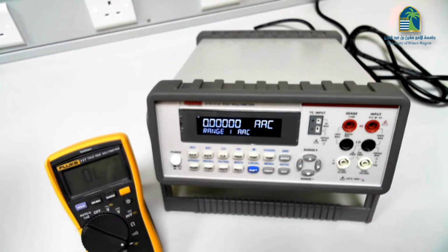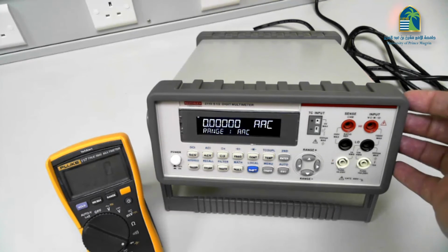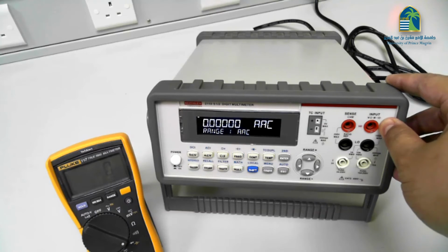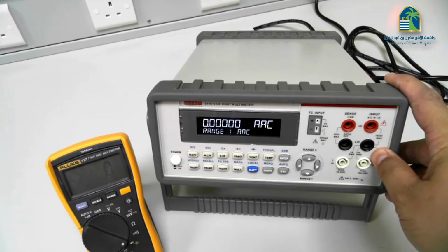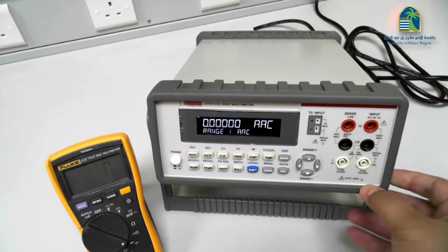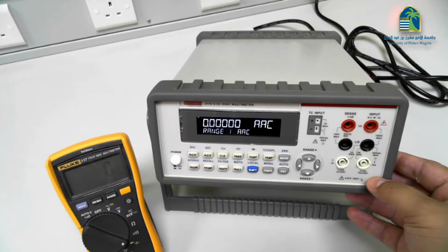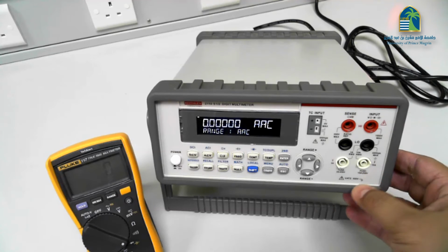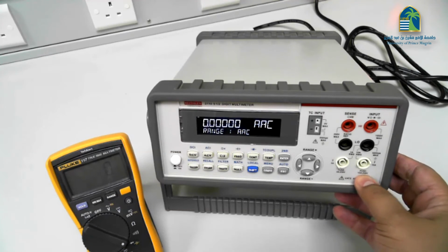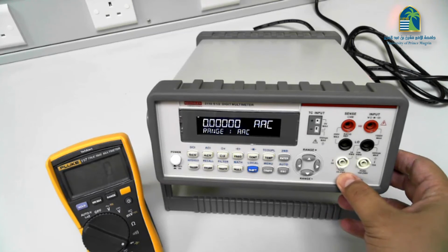Please be careful about this, because if you are not, you might just burn the fuse or damage the whole equipment. As for the Keithley multimeter, this red input is to measure the voltage, the resistance, the diode, and the capacitance. And this black input is the common, like in Fluke. These two white inputs are supposed to just measure the current. This one is for the high current up to 10 ampere or 15 ampere, as indicated over here. This one is more sensitive and can measure current up to 3 ampere.